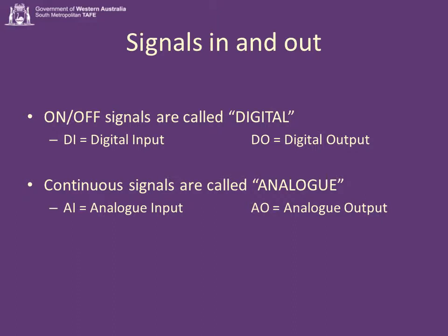Signals going in and out of a control system are of 4 types. On-off signals: things that are on-off we call digital. They only have 2 states, on-off. Could be on-off, start-stop, locked-unlocked, alarm-normal. We call them digital. If they're coming in, we call them digital inputs, DI. If they're going out, for instance to contactors, relays, solenoids, we call them digital outputs, DO.